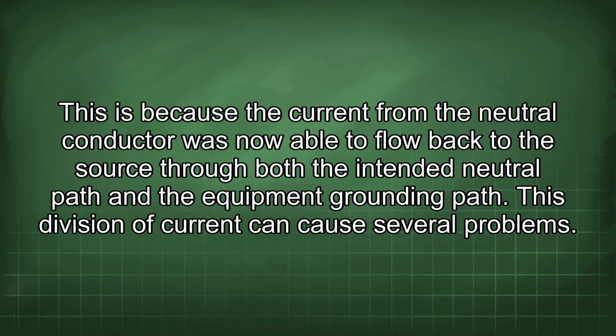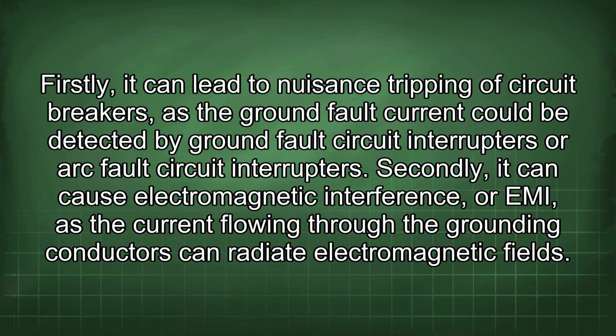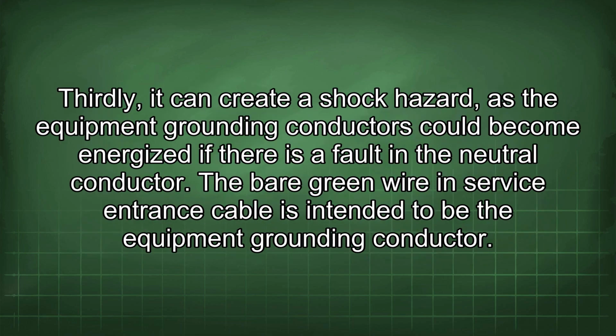This is because the current from the neutral conductor was now able to flow back to the source through both the intended neutral path and the equipment grounding path. This division of current can cause several problems. Firstly, it can lead to nuisance tripping of circuit breakers, as the ground fault current could be detected by ground fault circuit interrupters or arc fault circuit interrupters. Secondly, it can cause electromagnetic interference, or EMI, as the current flowing through the grounding conductors can radiate electromagnetic fields.